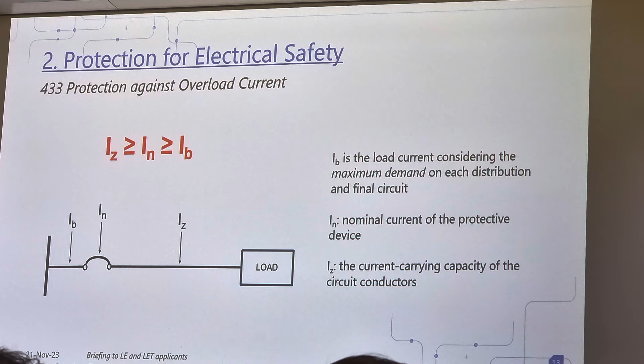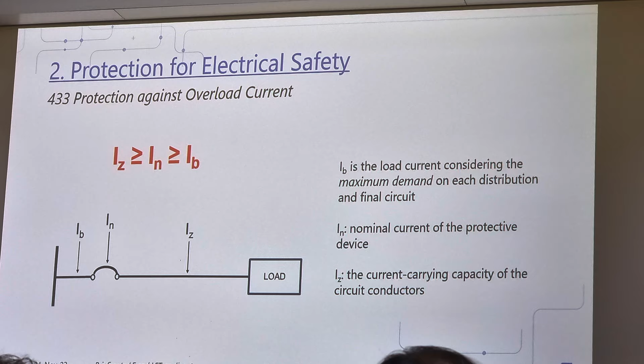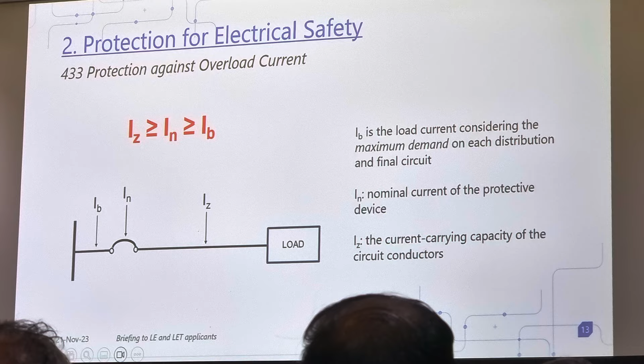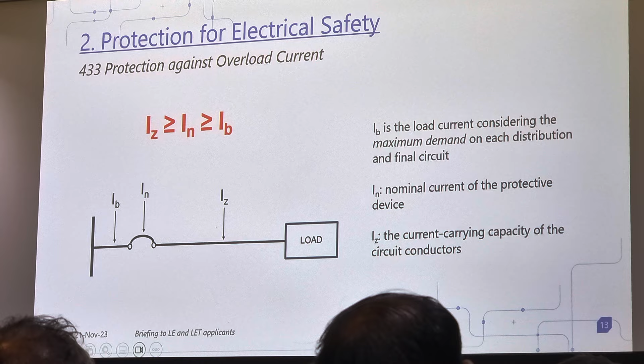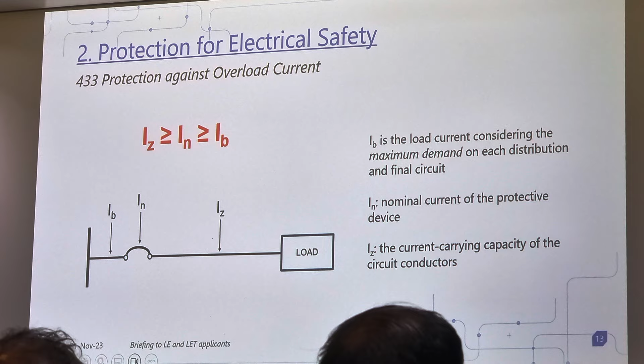Of course, we go further and say that sometimes you need overload protection. Because if we have overload protection for the motor, then you can change the formula because you don't have to afford the overload protection. Generally, for most of the circuits, you need to know that the maximum design current should be less than the current rating of the protective device, which should be less than the current capacity of the cable. So the cable can carry the current continuously because the current capacity is higher than the maximum current in the circuit.